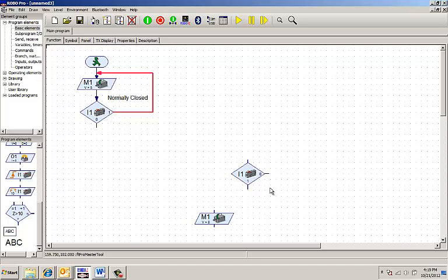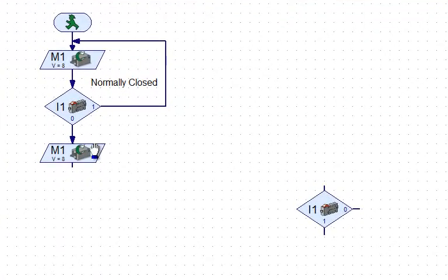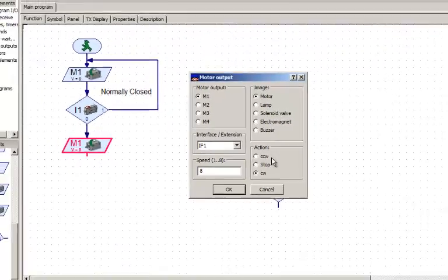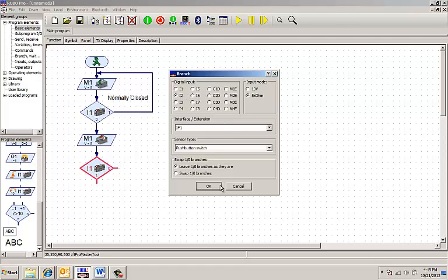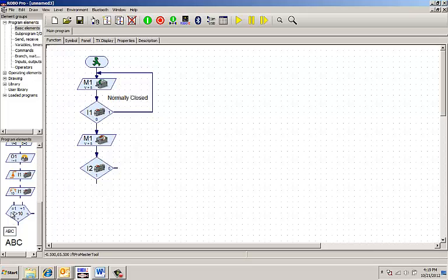All right. Now when it gets there, I1 changes from a 1 to a 0, and I want it to begin to run in the other direction. So I have a motor command, and I'm going to put in counterclockwise. Right? And then I want it to run towards I2. Alright, and I2 is wired normally open.